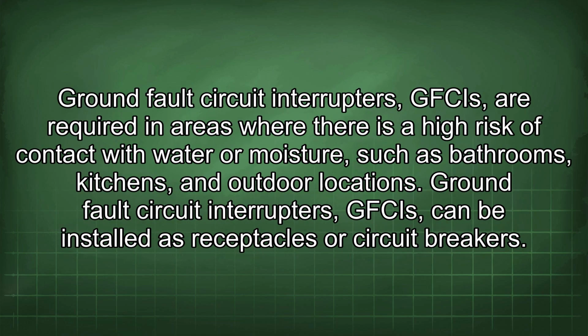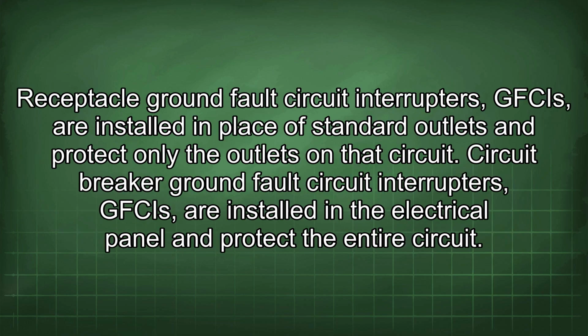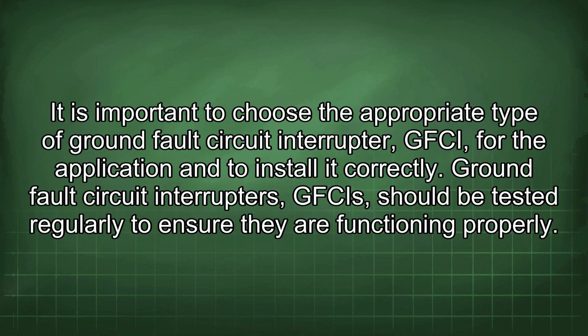GFCIs are required in areas where there is a high risk of contact with water or moisture, such as bathrooms, kitchens, and outdoor locations. GFCIs can be installed as receptacles or circuit breakers. Receptacle GFCIs are installed in place of standard outlets and protect only the outlets on that circuit. Circuit breaker GFCIs are installed in the electrical panel and protect the entire circuit. It is important to choose the appropriate type of GFCI for the application and to install it correctly. GFCIs should be tested regularly to ensure they are functioning properly.